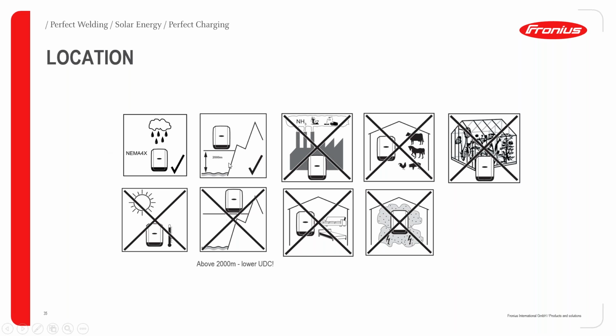It can be installed at altitude of up to 2,000 meters above sea level. Beyond that, you're definitely going to have issues with the DC operating voltage. So for industrial areas, because of the toxicity of some of the substances or components used in industries, we are advised that inverters don't come in contact with such toxic materials. And because of the noise, well, the noise is not that much from the fan, but we understand that some are quite sensitive to fan sound. So it's advised not to be installed in hospital wards or in living rooms. And of course, not places exposed to dusty surfaces.